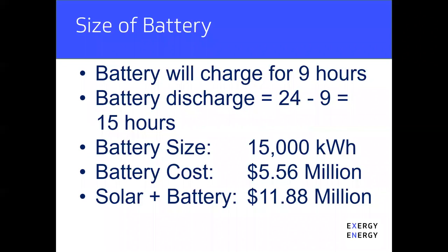But are we there yet? So what size battery do I need if I am going to be using solar? When we look at it, the battery is going to charge for about 9 hours a day. So this battery discharge is 24 minus 9, or 15 hours. So we've got a battery size that is about 15,000 kilowatt hours. And if you remember, it was $370 per kilowatt hour—we need 15,000 of those buckets, essentially. That's a battery cost of $5.5 million. If you add the solar onto that, it's almost $12 million.